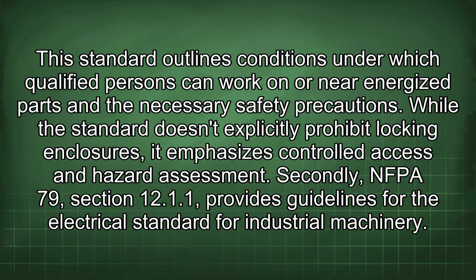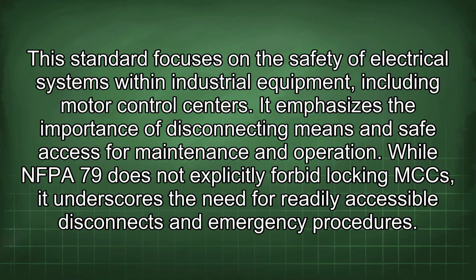Secondly, NFPA 79, Section 12.1.1, provides guidelines for the electrical standard for industrial machinery. This standard focuses on the safety of electrical systems within industrial equipment, including motor control centers. It emphasizes the importance of disconnecting means and safe access for maintenance and operation. While NFPA 79 does not explicitly forbid locking an MCC, it underscores the need for readily accessible disconnects and emergency procedures.